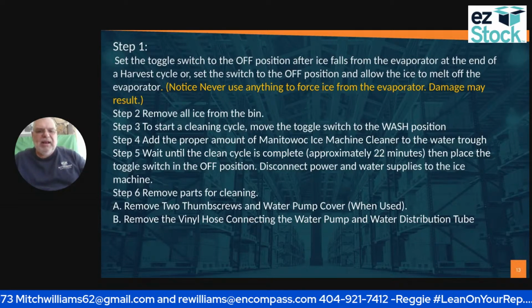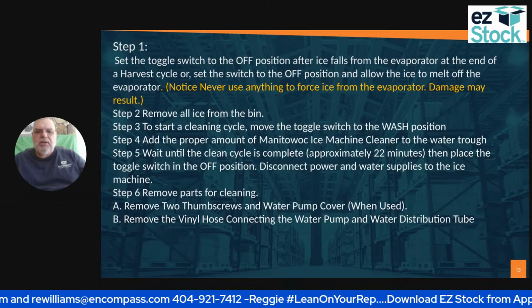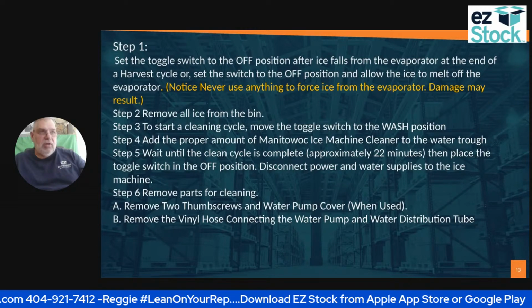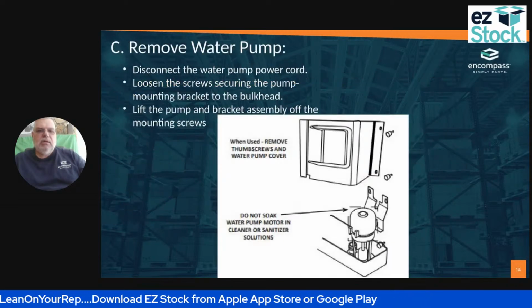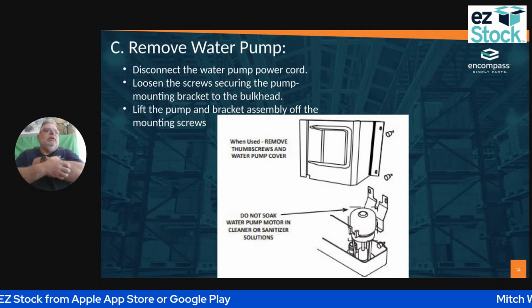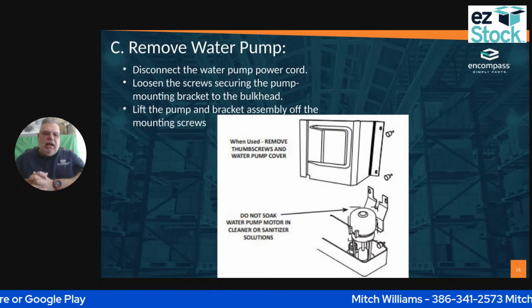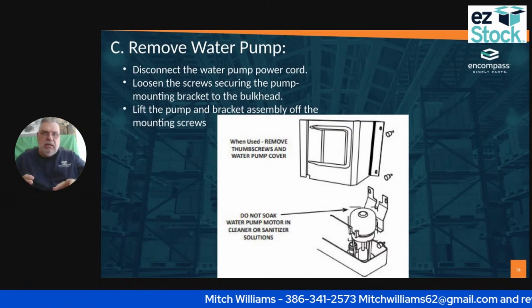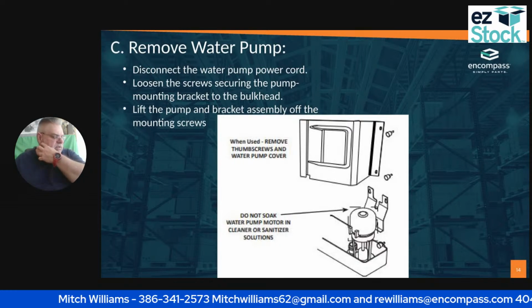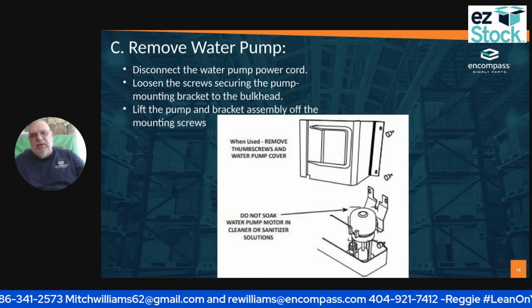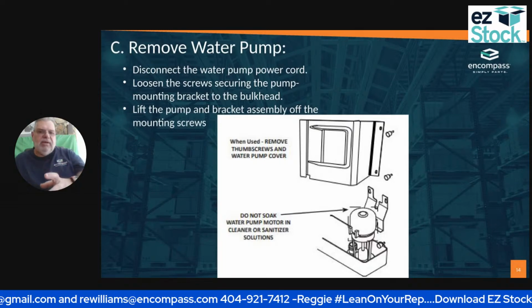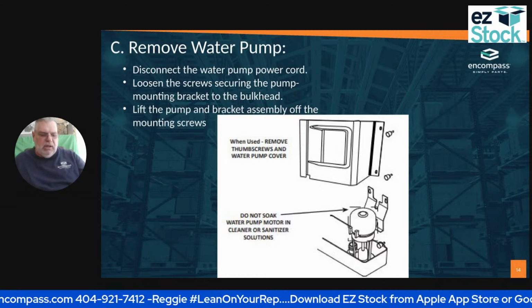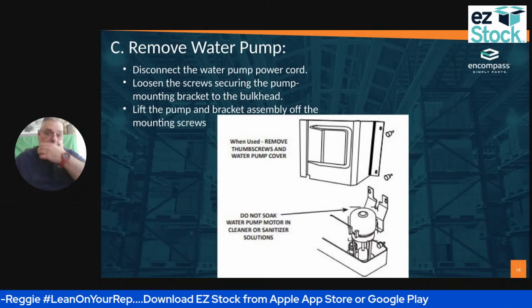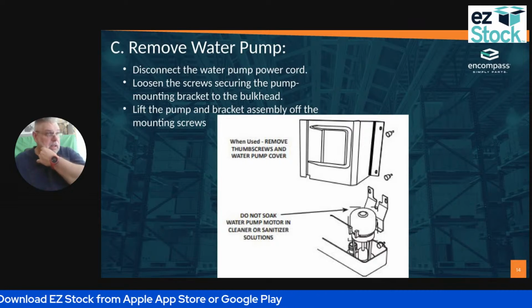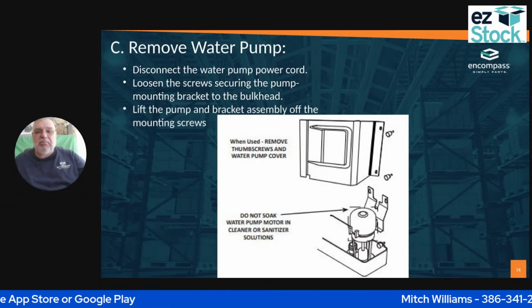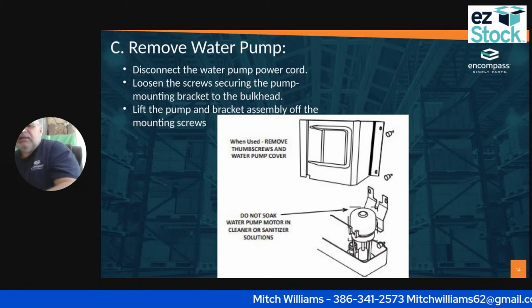Remove the vinyl hose connecting the water pump to the distribution tube. I've got to clean all of this and sanitize it. This is the number one reason, if I'm doing this in a restaurant, which you're probably not going to have this problem with because you're going to do this every time. But every 6 months, I've got to clean that. If I don't, the algae, the mold, the slime all build up in the area, and even on my door I'll get slime. This is what fails restaurants a lot of the times.